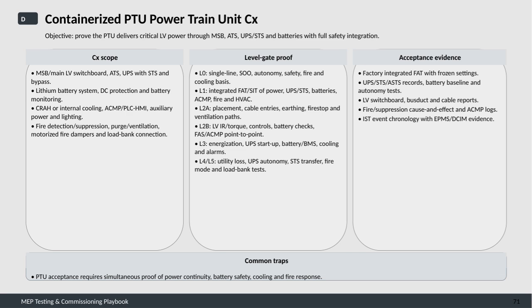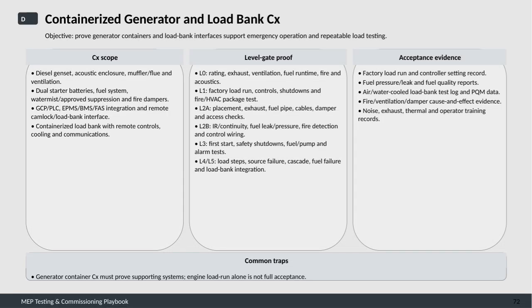On this final slide, we focus on commissioning of containerized generators and load banks. The main objective here is to confirm that the generator containers and load bank interfaces effectively support emergency operation and enable repeatable load testing. The commissioning scope covers a wide range of components. This includes a diesel genset itself, along with the acoustic enclosure, muffler, flue, and ventilation systems.